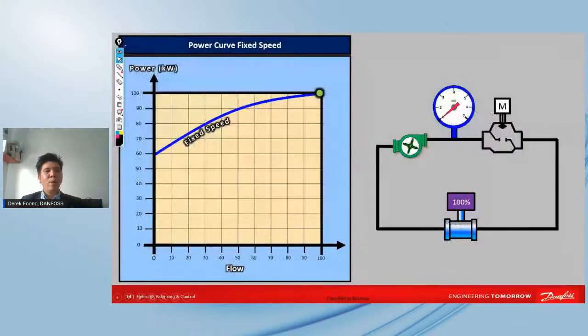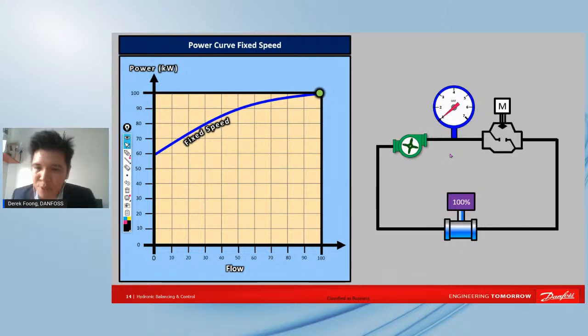All right, so another way to look at it is that if we look at systems that have a pump running a single loop, and you have a fixed speed pump without inverters, what happens if you actually close the control valve and regulate the control valve to about 50% of the flow rate? And this is a very simple comparison, and most of the end users want to have a simulation to look at this. So when, of course, the control valve closes, pressure builds up. And this is the flow meter. So we see like 50% of the flow rate.